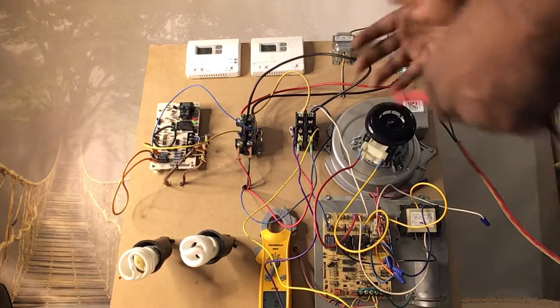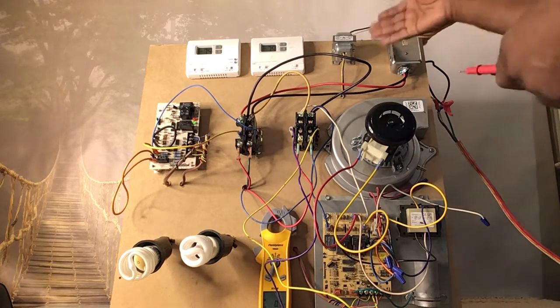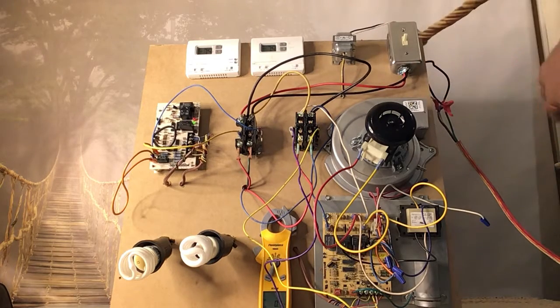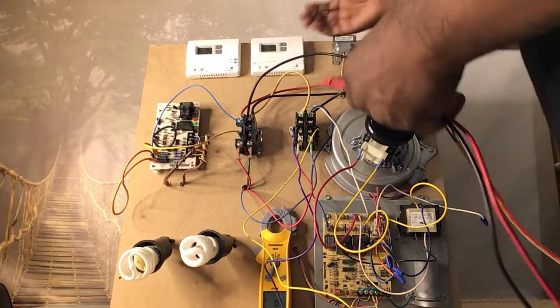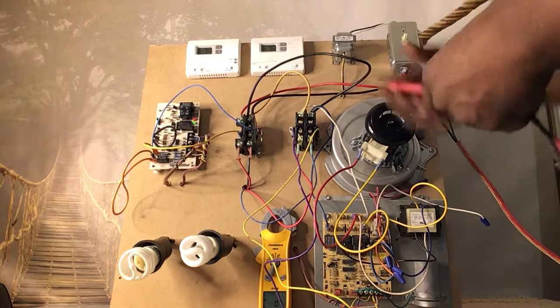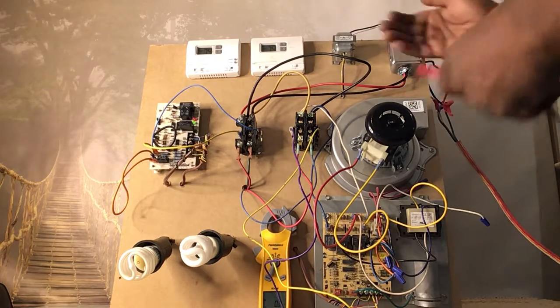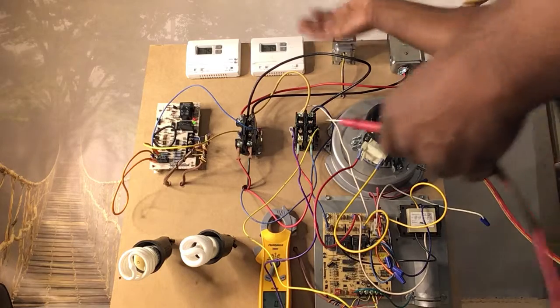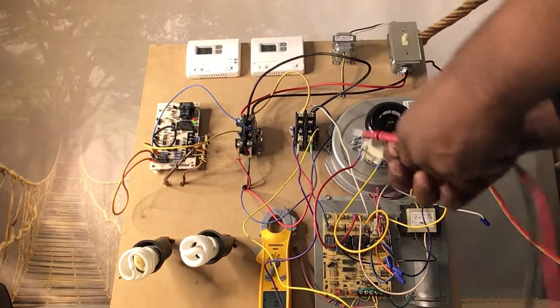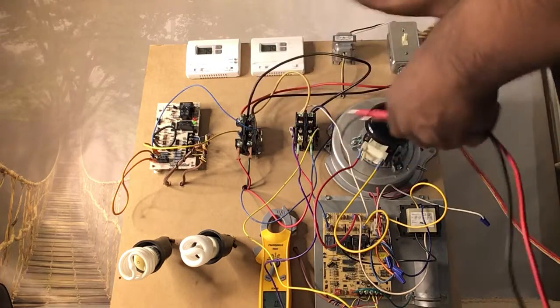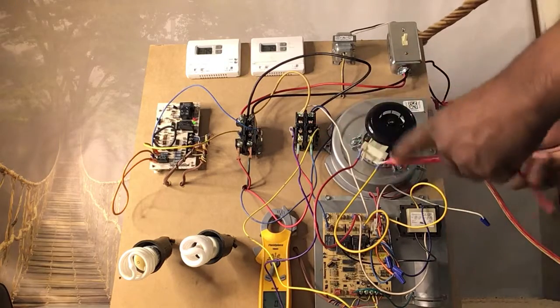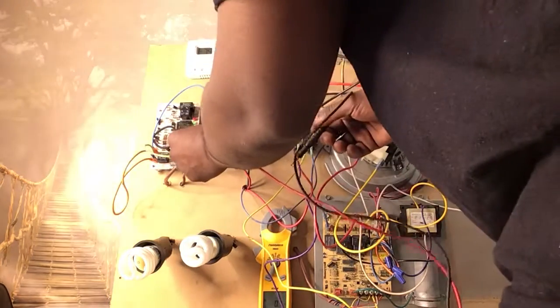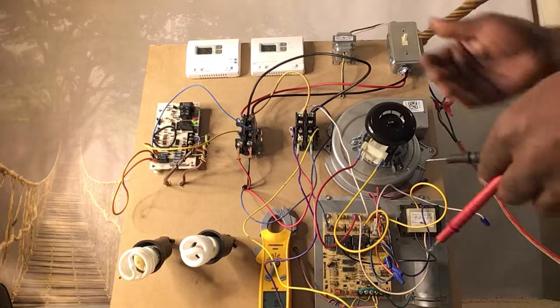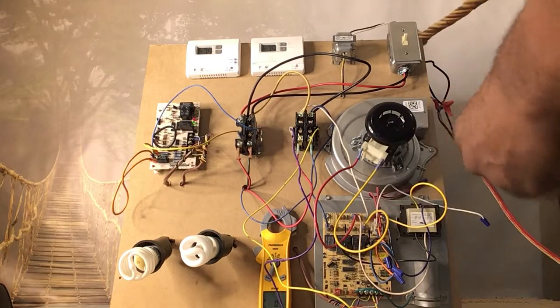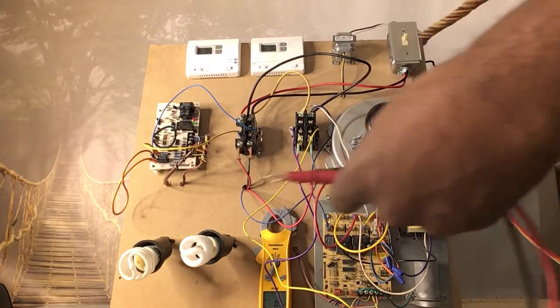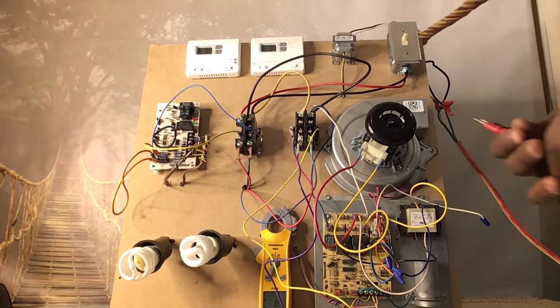Once you verify that your transformer has voltage and has 24 volts coming out of it, then you move on to your thermostat. You see if your thermostat has 24 volts on it. If it does, then you move down to your control board, either at your air handler or your outdoor unit. Make sure that you have 24 volts there. Then, once you have verified all of that, you know you've got power. There may be some other things wrong with your system.